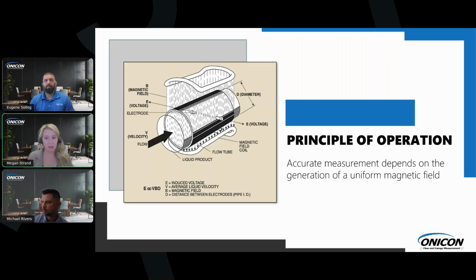We offer PTFE, polypropylene, and ebonite, which Gino discussed earlier, depending on your application temperature. Outside of that stainless steel meter tube is where the coils are mounted, and then there is a shroud on the outside. As I mentioned, the meter tube itself, which is what could come in contact with the water, is always stainless steel. But for the shroud, when you're ordering the meters, you'll notice you can order carbon steel or stainless steel. Carbon steel is standard, and that's what we recommend for most of our applications.